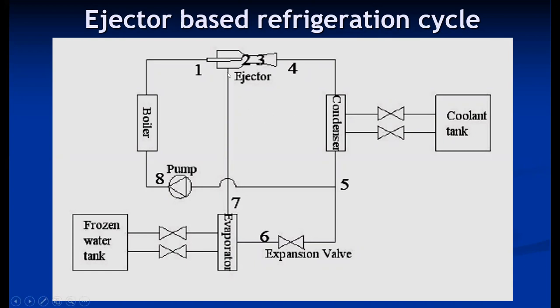Let us take a review of the basic cycle. The compressor is replaced by three devices: a pump, boiler, and ejector, performing the three basic functions of a compressor. The ejector sucks the refrigerant; the pump increases pressure; and the boiler increases temperature. The refrigerant at the outlet of the ejector is at high pressure and high temperature vapor. It enters the condenser where it gets condensed. At point five, it divides into two streams — one stream goes to the boiler and the other expands through the expansion valve before entering the evaporator, where it takes up heat from the substance to be cooled and gets evaporated.